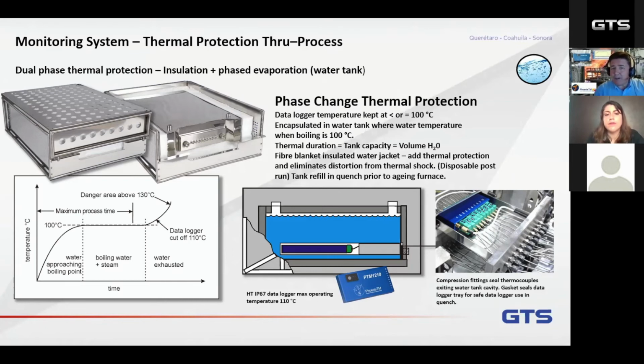So if we develop a system where the tank has enough capacity to last the duration of the furnace, we will be able to maintain the temperature of the data logger at 100 degrees. Now, the data logger is capable of operating up to 110 degrees, so it's working very safely in that situation.